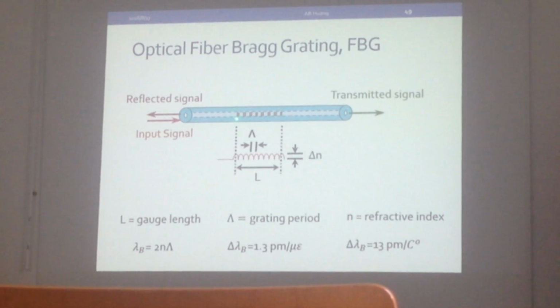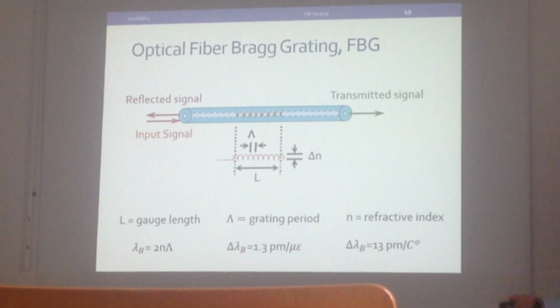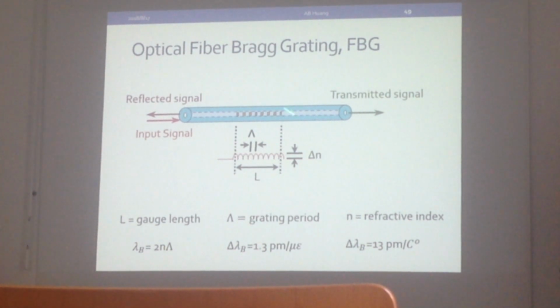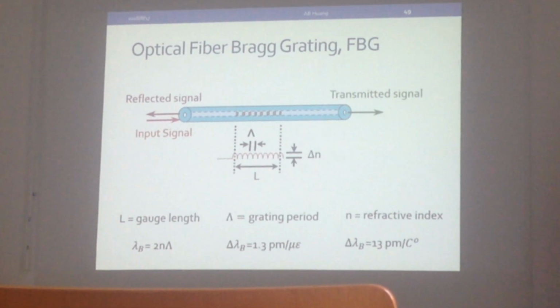The space between the dark and light, it's not necessarily really dark and light, it just changes the refractive index. We call it the grating period. It's capital lambda. When the light source comes in from here, usually we call it broadband light. It's laser light with a wide range of wavelengths. When it hits this FBG, part of it is reflected back. The reflected wavelength is related to this capital lambda. So when this part of the FBG is stretched, this lambda increases. Then the reflected wavelength increases. So we use the wavelength shift to determine what kind of strain this part of the FBG is experiencing.